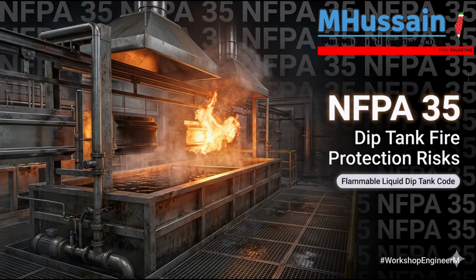The physical connection has to be utterly flawless. You can't just wrap a wire loosely around a pipe and call it grounded. Right. The standard specifies that permanent grounding connections must be made with heavy-duty electrical cable lugs, bolted clamps, brazing, or welding. It must be mechanically robust so it cannot be accidentally knocked loose. But where it gets really tricky is with portable equipment, like grounding a 55-gallon drum before you pour from it. Oh, definitely. The standard dictates that temporary bonding clamps must be the opposed point type. This is a tiny detail that layout engineers and safety managers must mandate on the procurement sheets. It is a massive detail, actually.